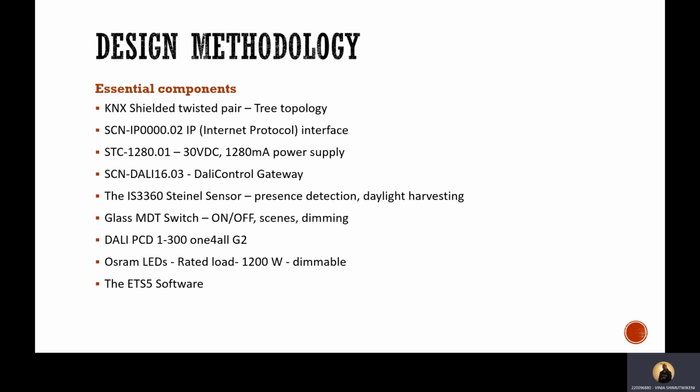For the design methodology, I have the most important components. I've used a shielded twisted pair in a tree topology. I have an internet protocol interface and a 30 volt power supply that supplies 1280 milliamps. I also have a DALI gateway, or DALI controller, and a Steinel IS3360, which performs presence detection and daylight harvesting.